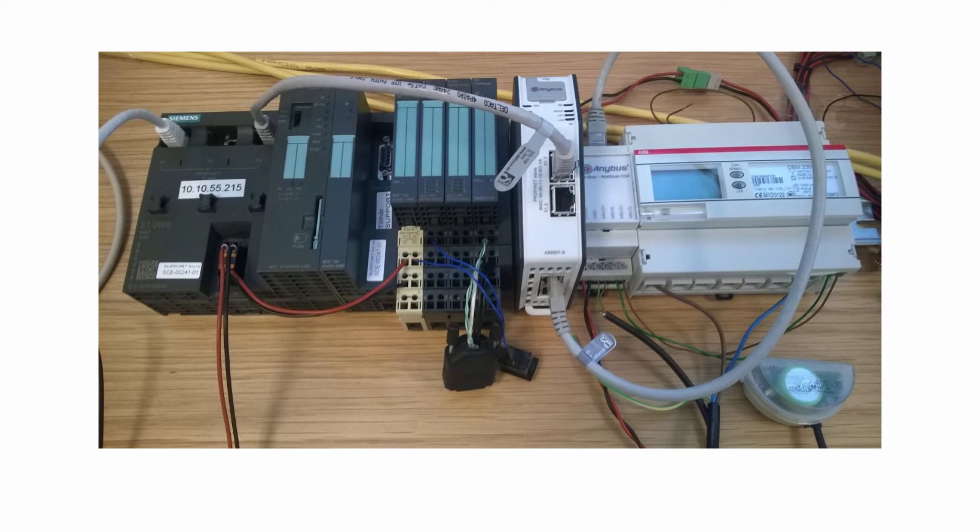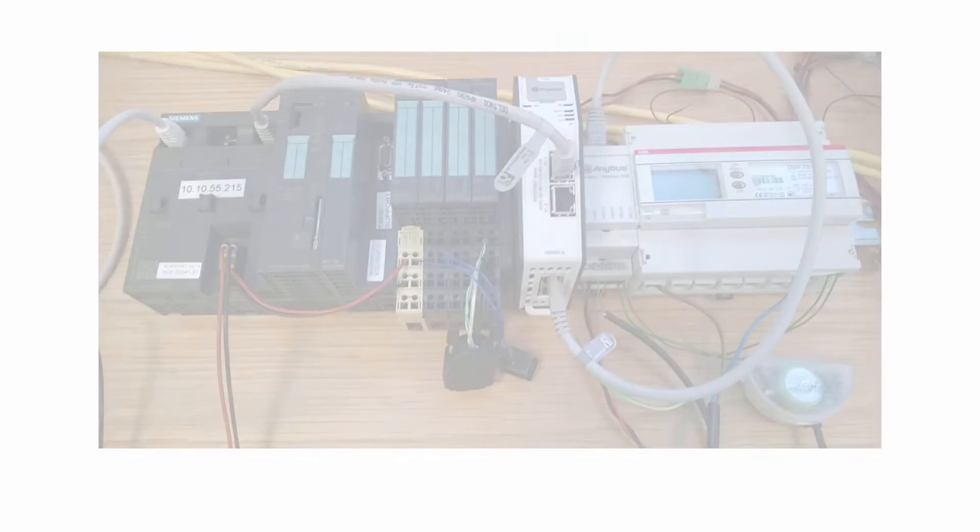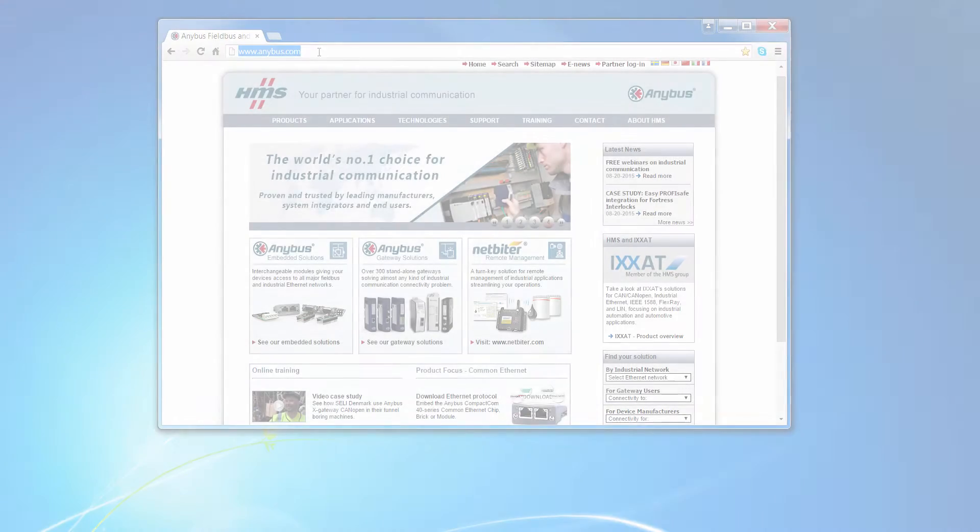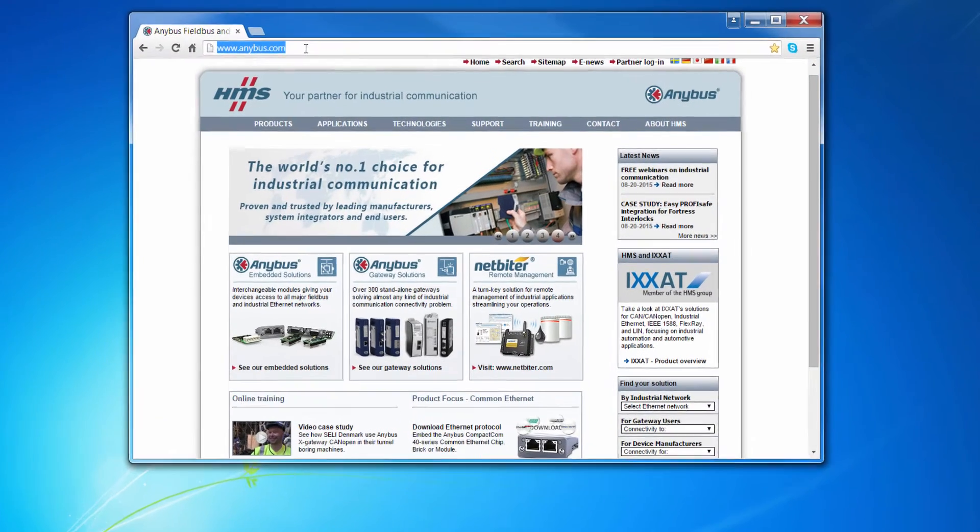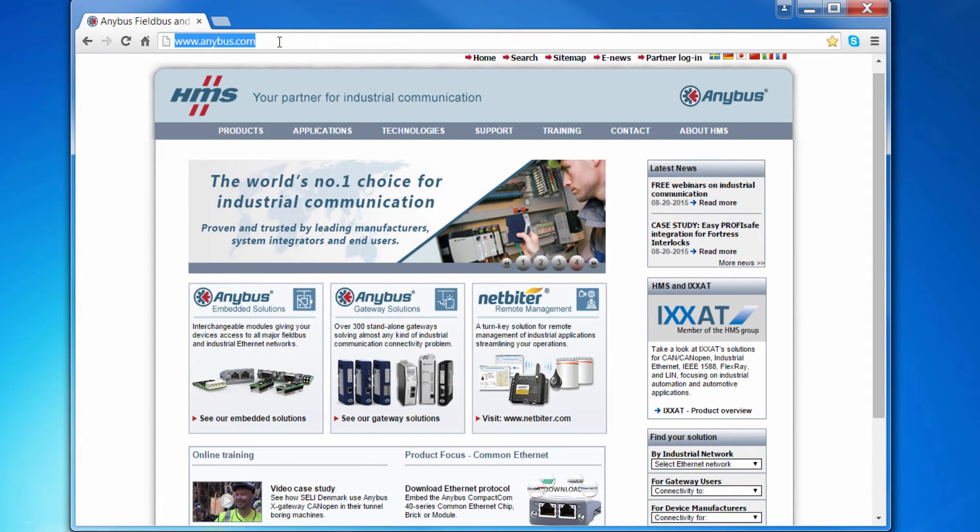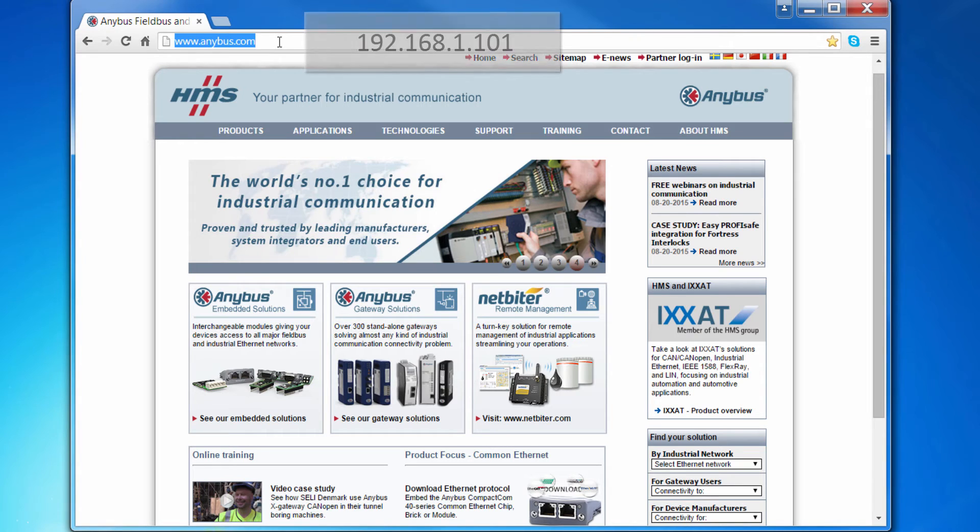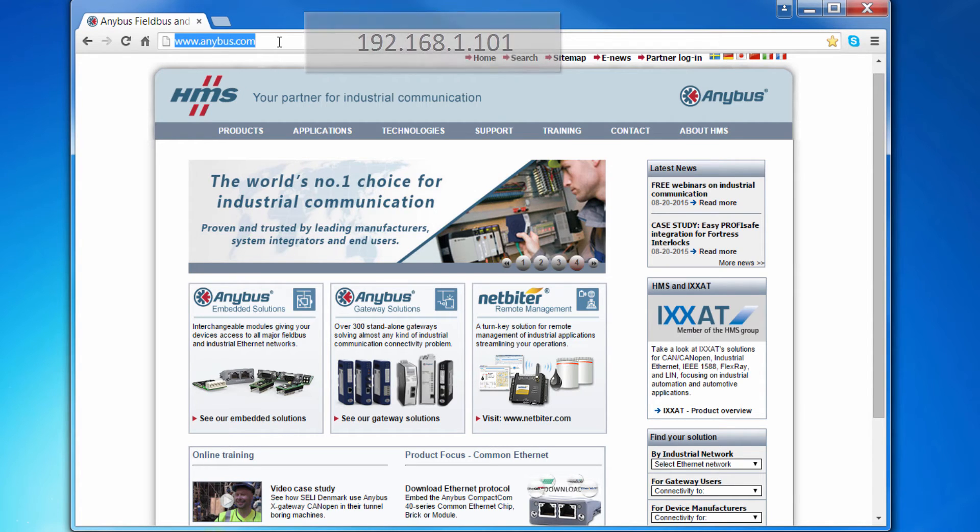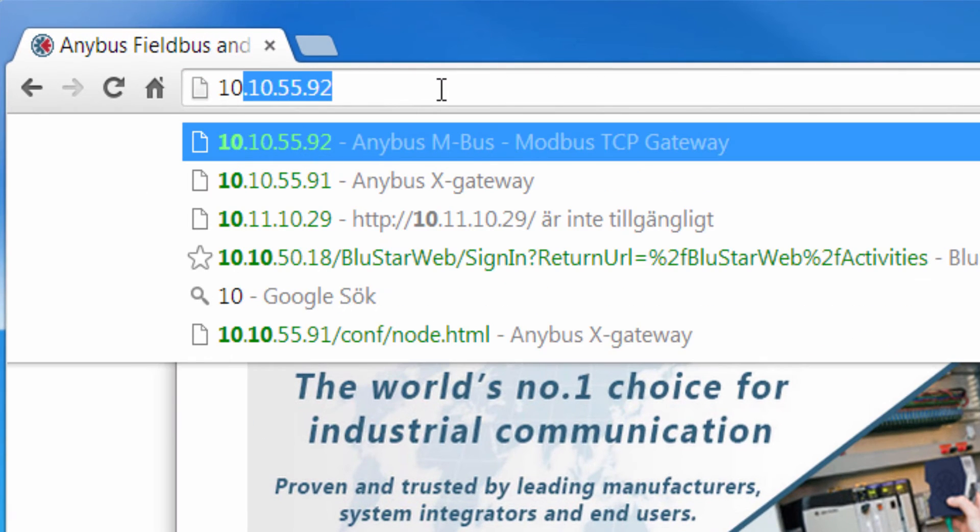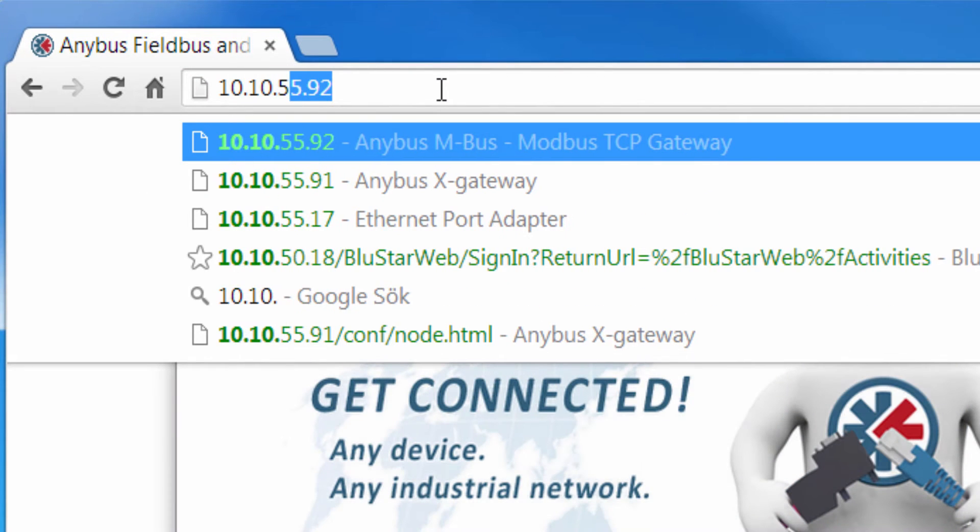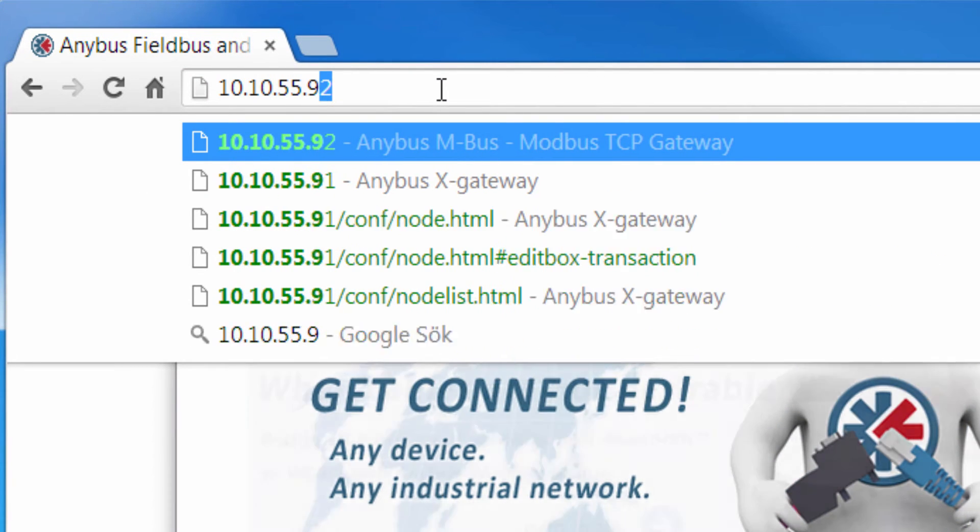After connecting all devices to the network, I first log in to the MBUS to Modbus TCP gateway. I do this by typing in the IP address of the gateway. The default IP address for the gateway is 192.168.1.101, but in this case I am using 10.10.55.92.